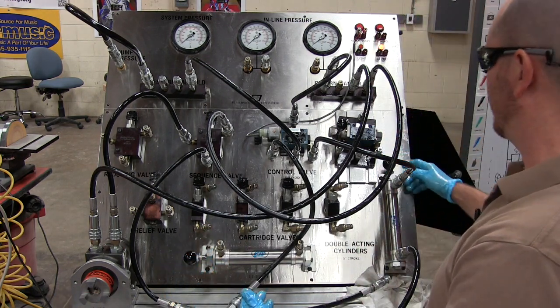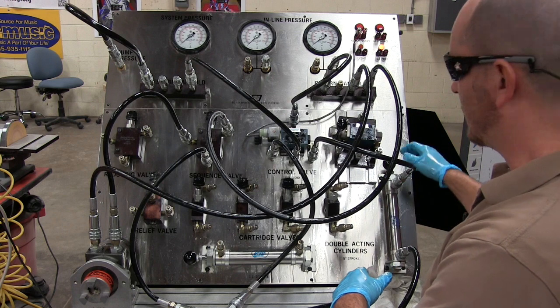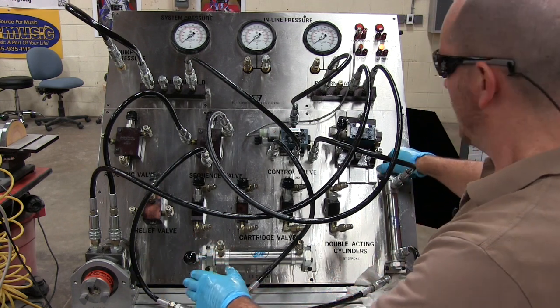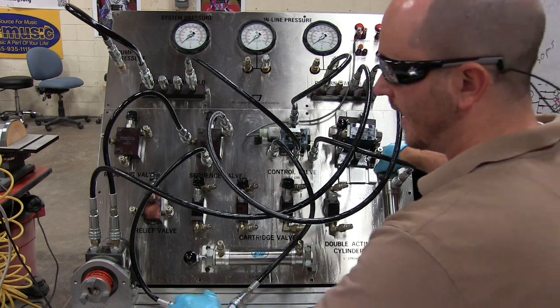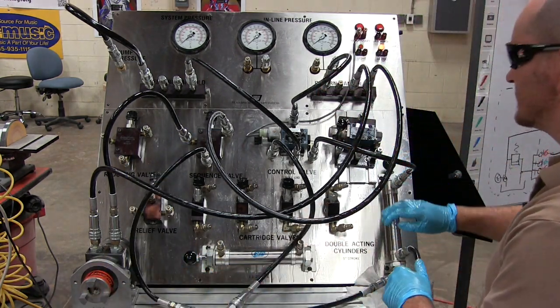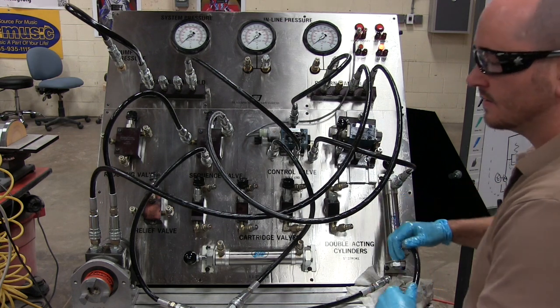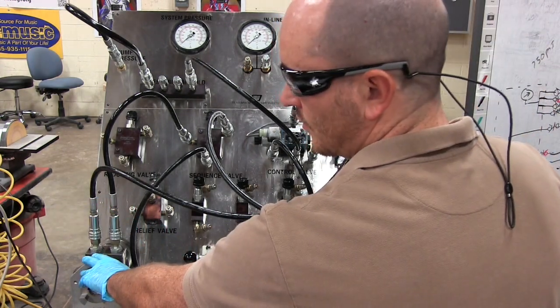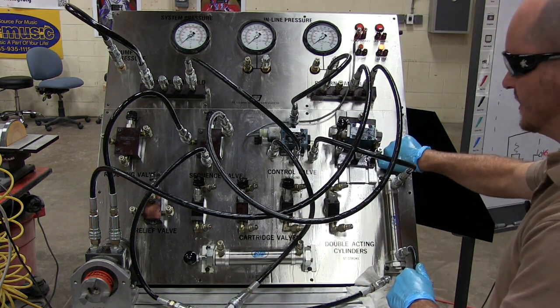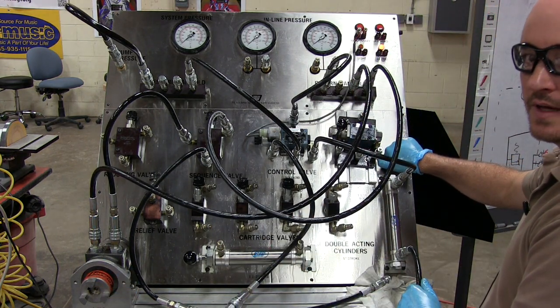Another example would be a clamp and drill or a clamp and rotate where it has to be clamped all the way. Then my hydraulic motor sequence is on. So the sequence is cylinder extends, motor runs. As soon as this thing is not in the extension position, the motor shuts off.